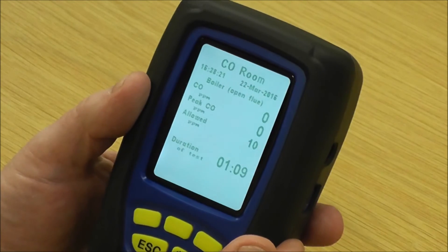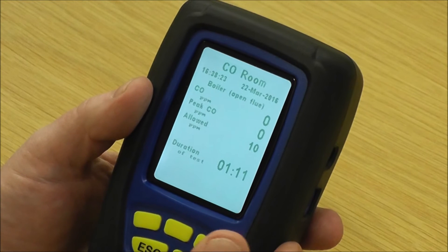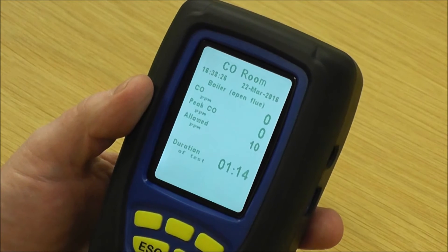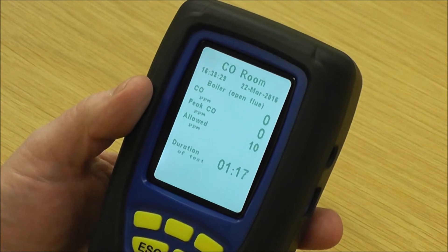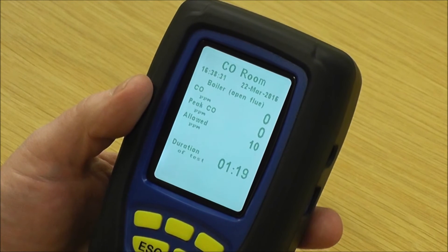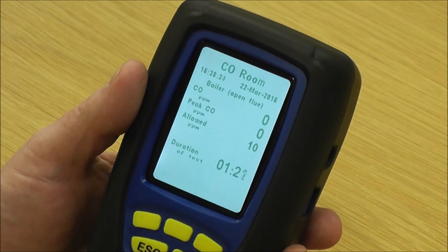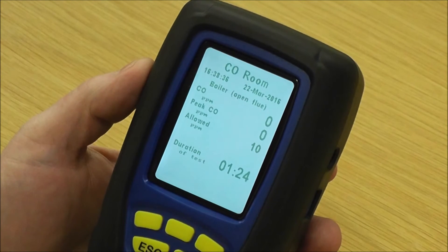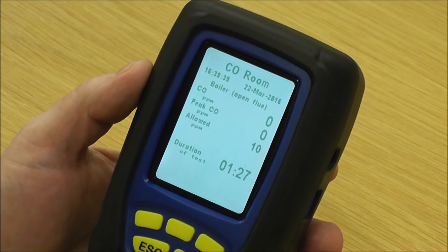If the readings were unstable or high — for instance, if it exceeded 30 parts per million while you were doing the test — you don't want to wait 15 minutes to find out you're over 30 ppm. So it's got a personal alarm built into it, and it will alarm to tell you that you need to turn the analyser off and vacate the building.